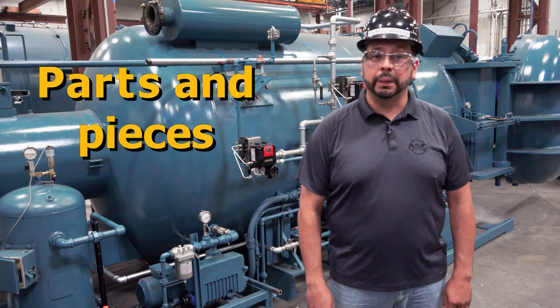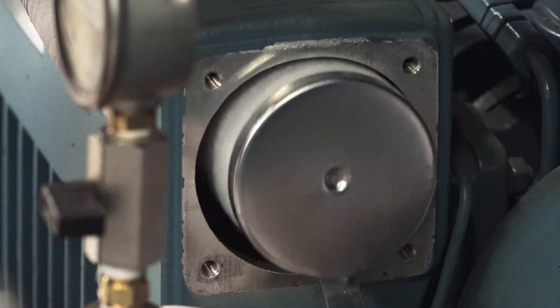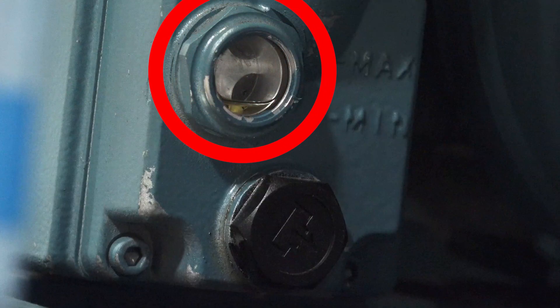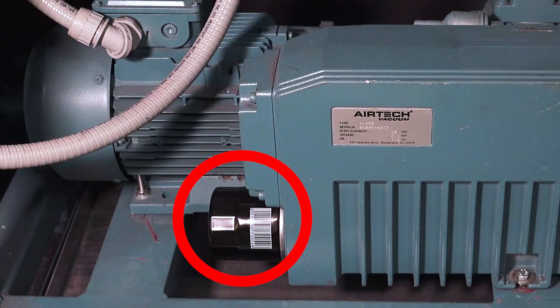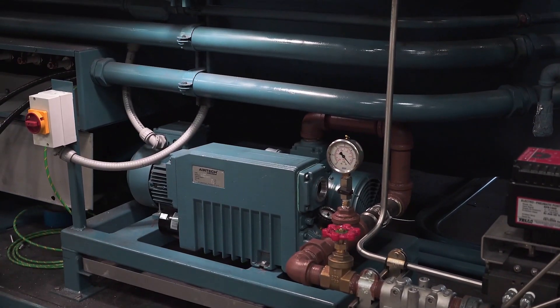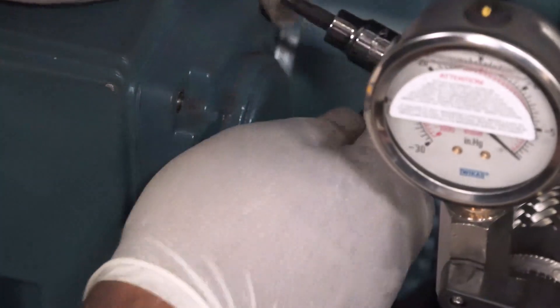Before we get into maintaining your pump, let's quickly cover the parts and pieces on the pump you'll need to get familiar with. There is an exhaust filter gauge that detects if the exhaust filter inside the pump is clogged. If you unscrew this gauge, you'll access the oil filling port. Directly below this is a sight glass to check your oil level, and below this is the oil drain port. There is also a spin-on oil filter located on the other end of the pump. The pump also has inlet and exhaust filters. The inlet filter is inline to the vacuum pump between the receiver tank and the pump, and the exhaust filter is located internal to the pump and can be accessed by removing the exhaust filter cover.